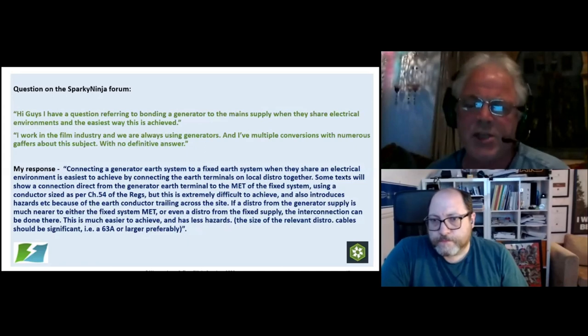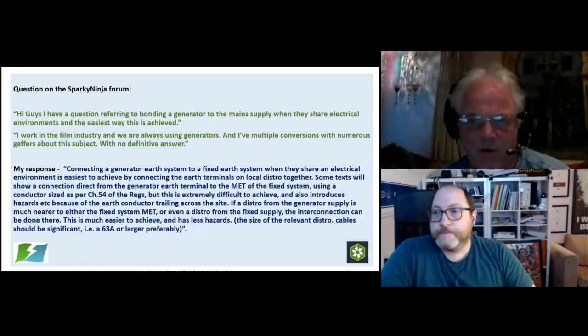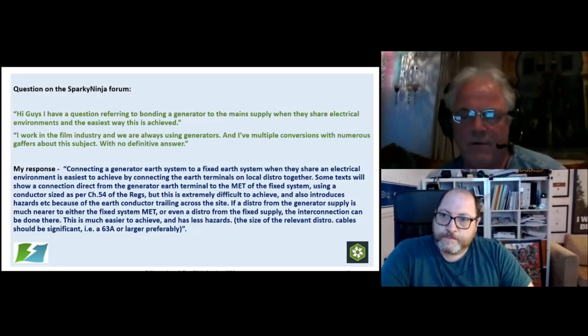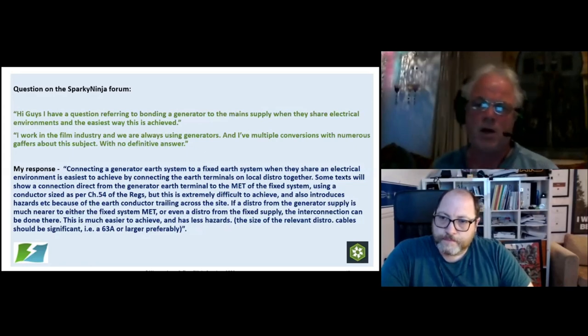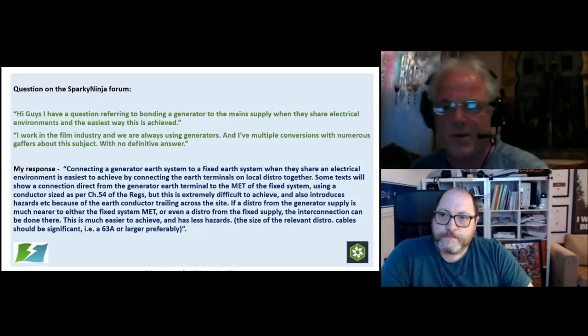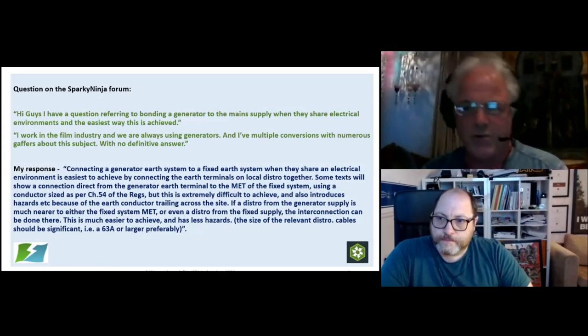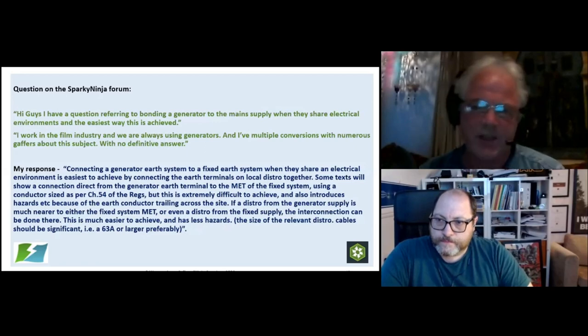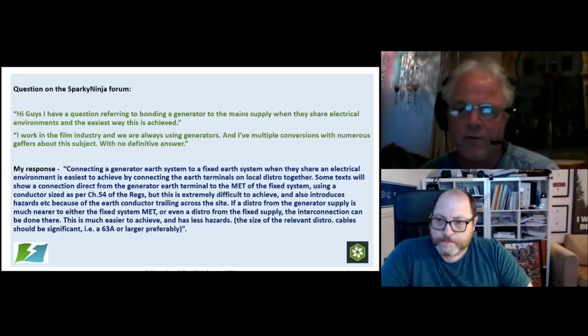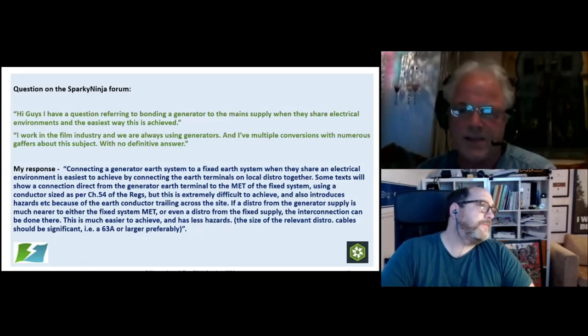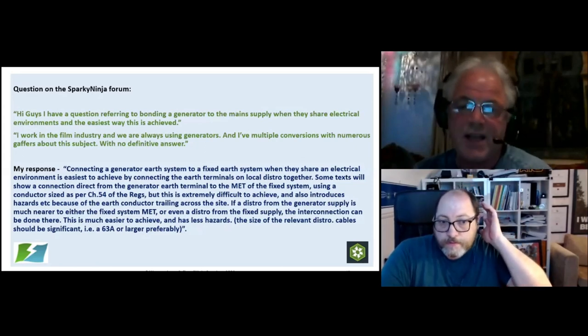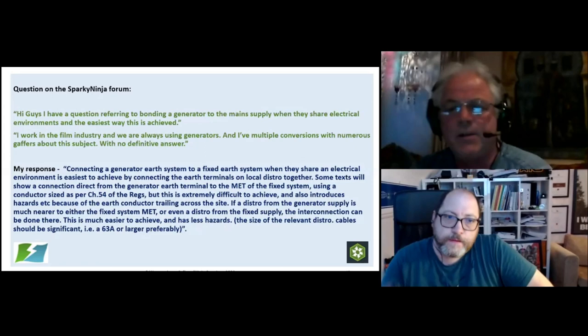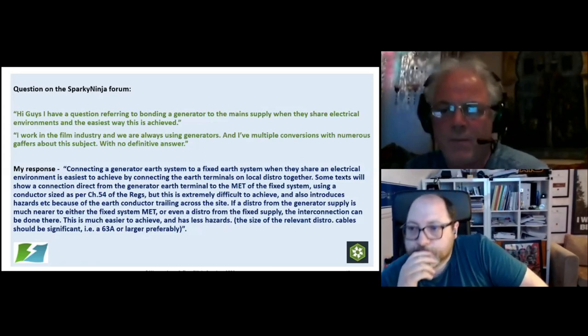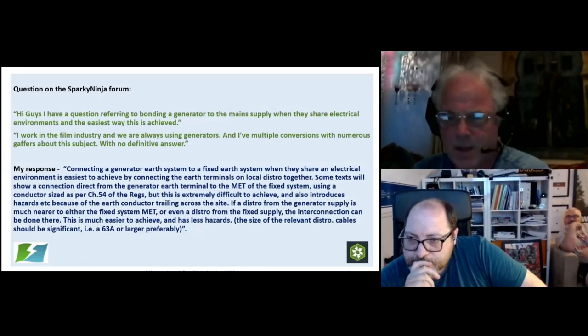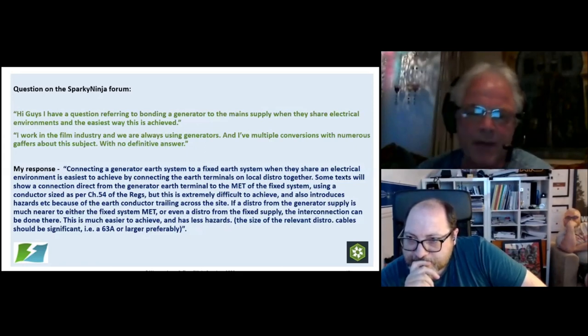Okay, so an easier way of overcoming this, and something that I've used myself, is if you've got a distro coming off your generator, so you've got a large cable feeding your distro, which might be inside the building. Your distro is much closer to your fixed installation. If you've got a distro off your fixed installation and a distro off your generator, you could just put an earth conductor between those two. They're much closer together, yeah? And you are effectively linking them together, achieving the same thing, but in a much easier, much more practical sense. So that was my answer.